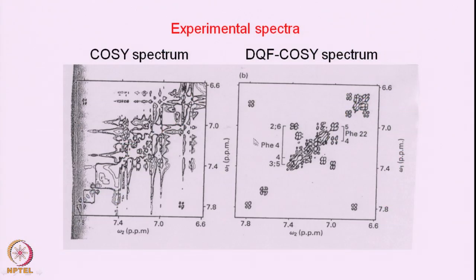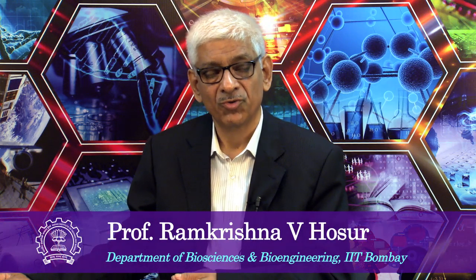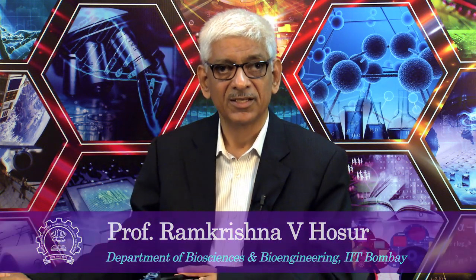We chose here a double quantum signal and converted it into observable single quantum by applying the third pulse — a slightly modified pulse sequence. This is a very general phenomenon: one can do this for various kinds of filters and select different pathways. For example, to select Z-magnetization you use a different kind of phase cycling — changing phases x, y, minus-x, minus-y and using different addition/subtraction combinations in the receiver. This illustrates the general strategy of selecting coherence transfer pathways in two-dimensional spectra.